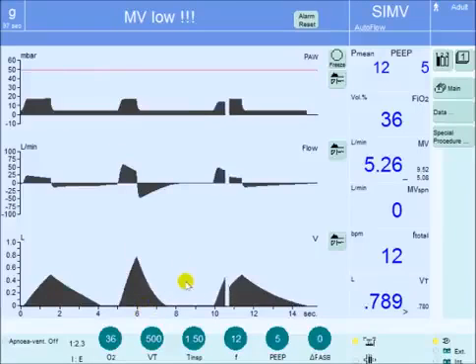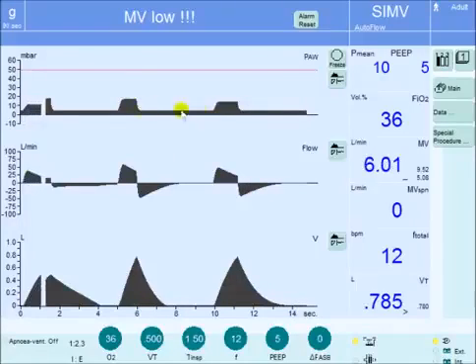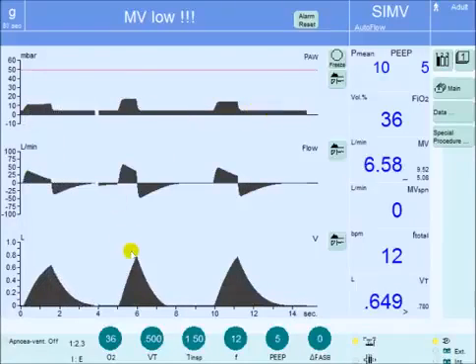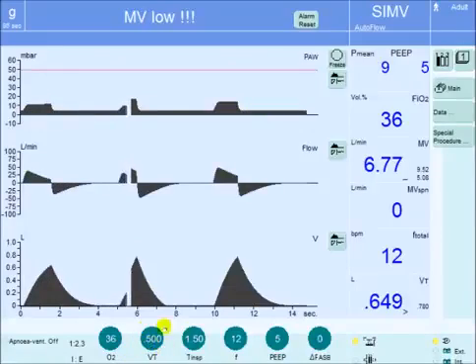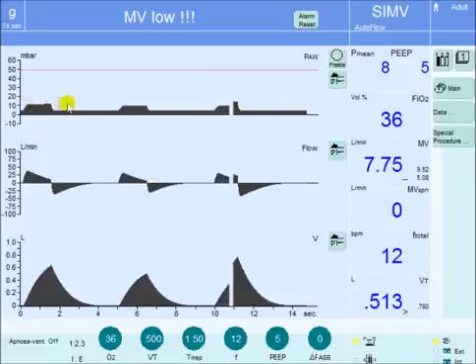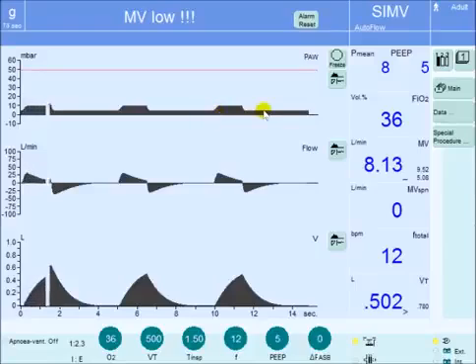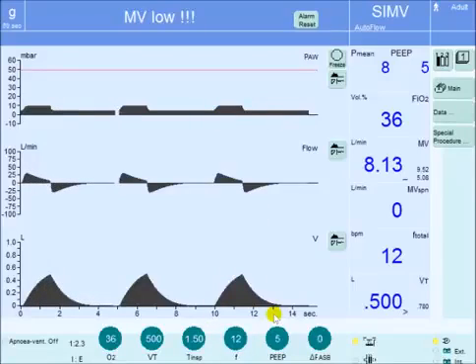At that point, the pressure will start going down gradually, until you get to the same tidal volume level that is targeted by the machine. So the pressure goes down again, 2-3 cm each breath, until you get to the minimum pressure required to deliver that target tidal volume.